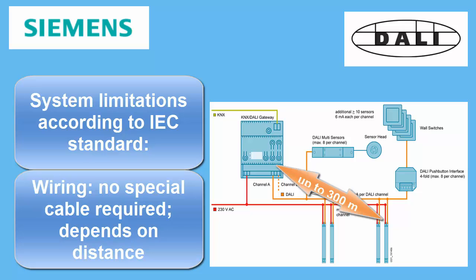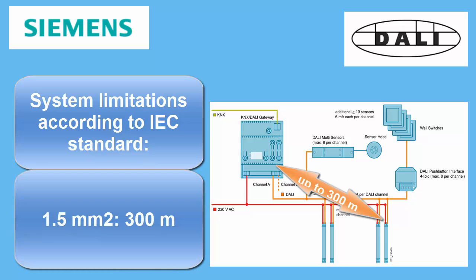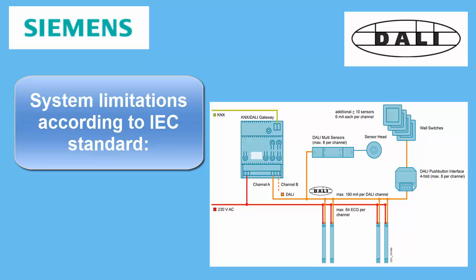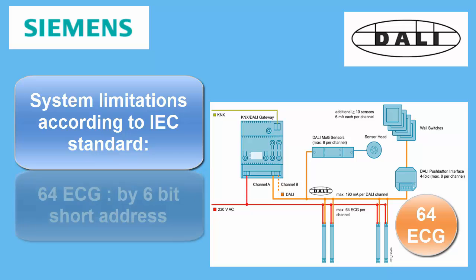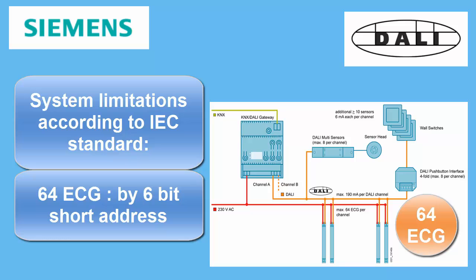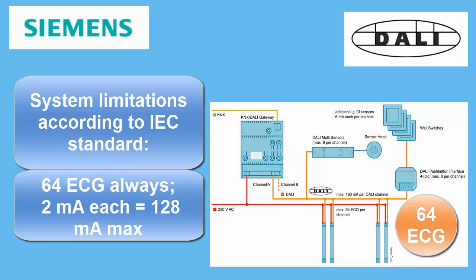The maximum range of 300m can be obtained by using 1.5 mm² cable cross-section. The maximum number of ballasts on a DALI line is 64, represented by the 6-bit short address. There is no reduction in the number of ballasts for reasons of high current consumption, since the DALI standard requires ballasts not to exceed 2mA per ballast. Therefore, you can always use 64 ballasts per line.